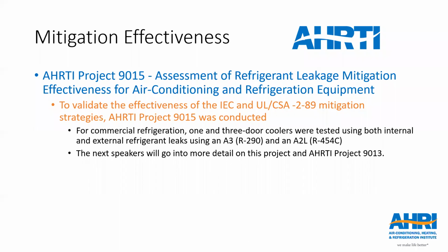So to evaluate the effectiveness of the mitigation techniques used in the 2-89 and the 2-40 standard for air conditioning equipment, AHRTI project 9015 was initiated. For commercial refrigeration equipment, the project's purpose was really to validate the mitigation techniques and test methods in the IEC version of 2-89 and to help inform any national deviations being proposed in the UL and CSA version.